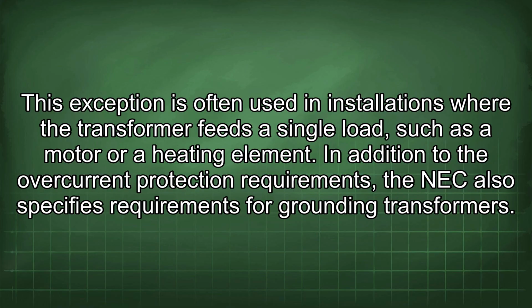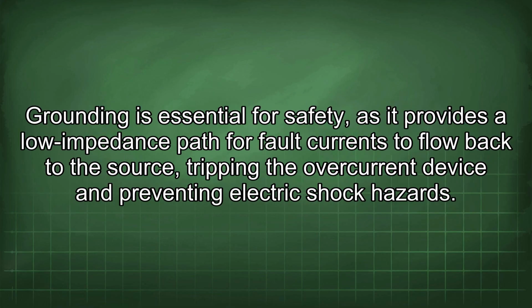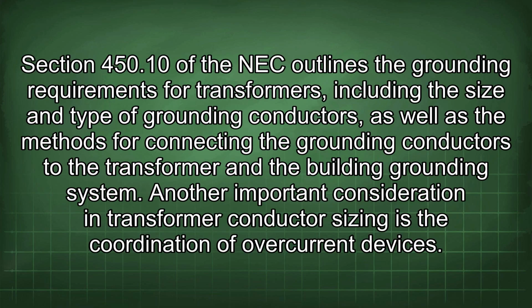In addition to the overcurrent protection requirements, the NEC also specifies requirements for grounding transformers. Grounding is essential for safety, as it provides a low impedance path for fault currents to flow back to the source, tripping the overcurrent device and preventing electric shock hazards. Section 450.10 of the NEC outlines the grounding requirements for transformers, including the size and type of grounding conductors, as well as the methods for connecting the grounding conductors to the transformer and the building grounding system.